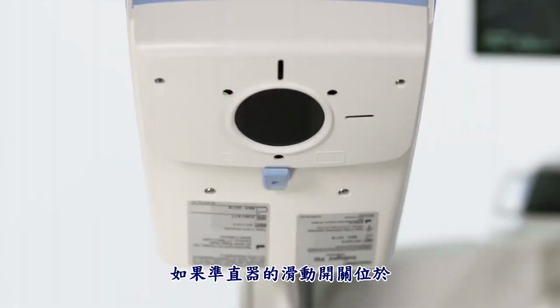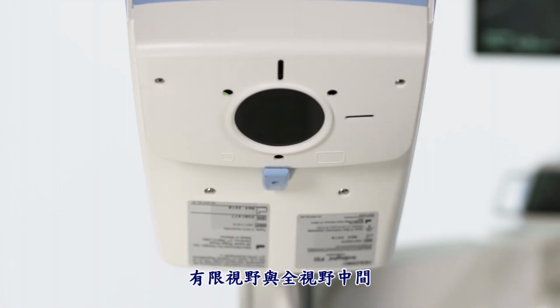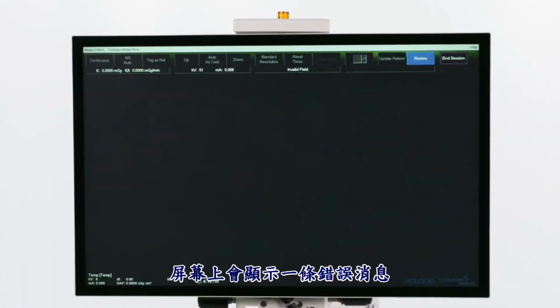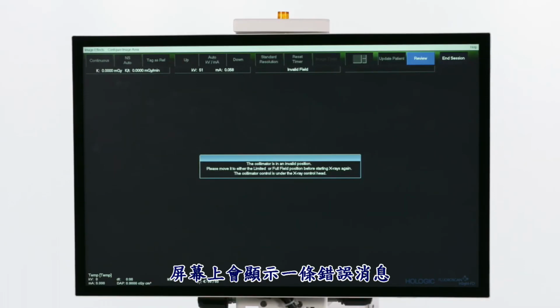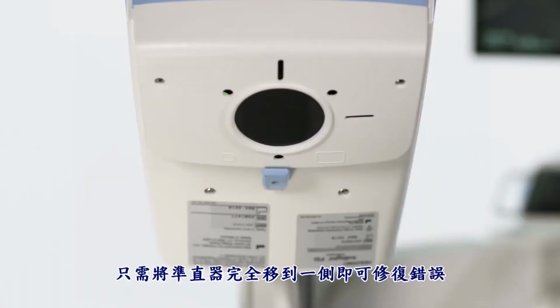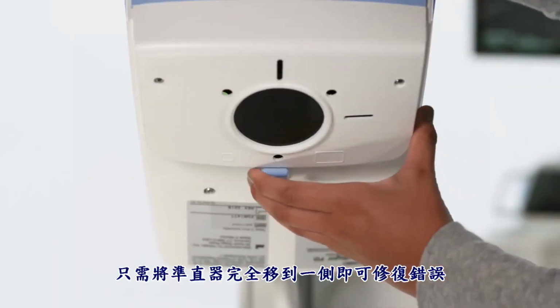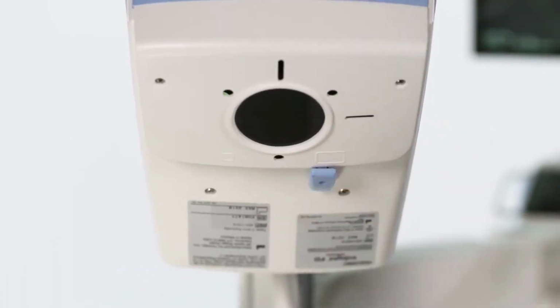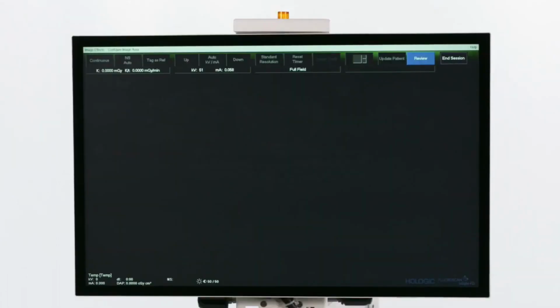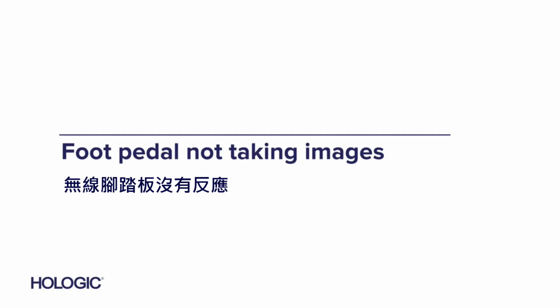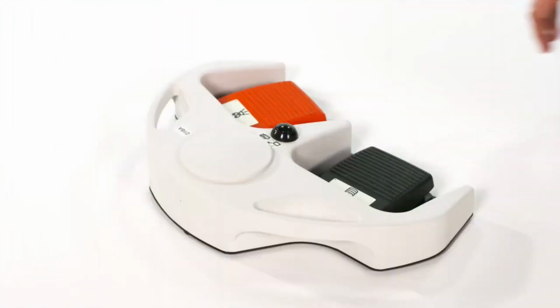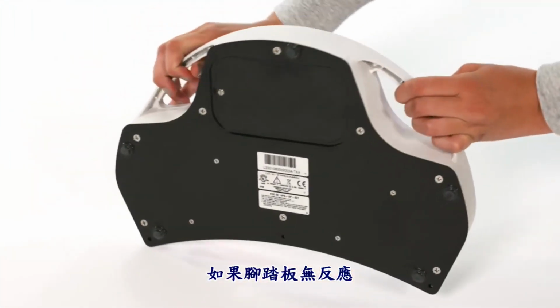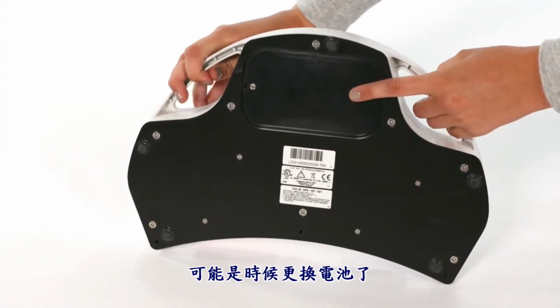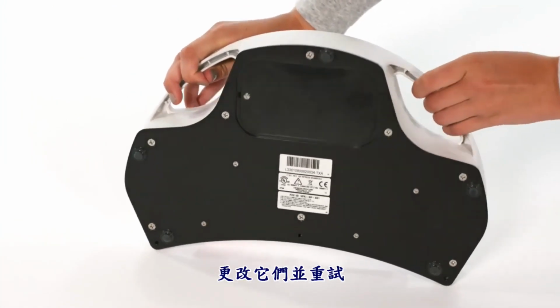If the collimator is left in between the limited view and full field view options, an error message will show up on the screen. Simply move the collimator fully to one side to fix the error. If the foot pedal is not taking images, it is likely the time to change the batteries. Change them and try again.